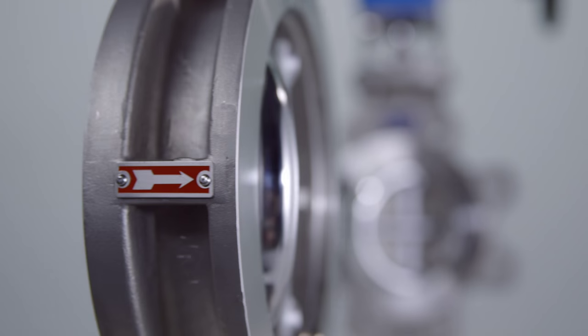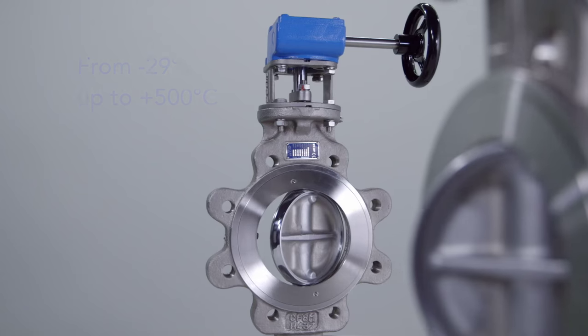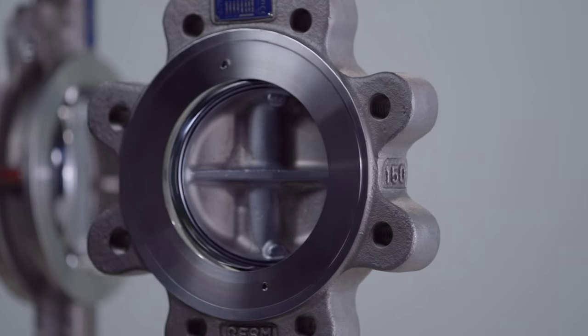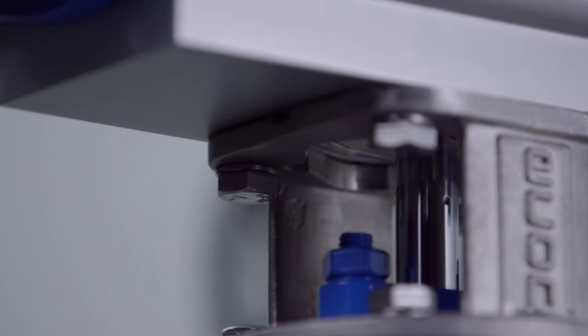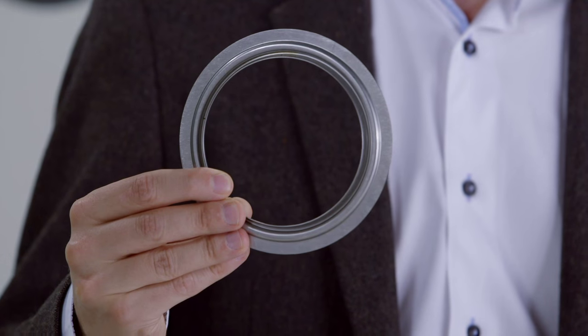Econ high-performance double eccentric valves can be used up to 500 degrees centigrade and are available up to DN 1200 / 48 inch. The ISO direct mount top flange facilitates the installment of any actuator. This valve has a primary PTFE and a secondary fire-safe Inconel seat.